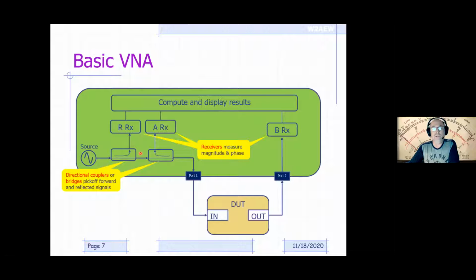And then all of these signals, the reference signal, if you will, that's being applied, the reflected signal coming back, and the transmitted signal going through the DUT are all measured in these receivers, and they're commonly called the R, or reference receiver. The A and B receivers will measure the reflected energy and the transmitted energy. So these receivers essentially measure the magnitude and phase of the forward, reflected, and transmitted signals. And then all those results are collected and computed inside a computer or microcontroller inside the VNA to display results in various formats. Quite simply, that's what a VNA does.